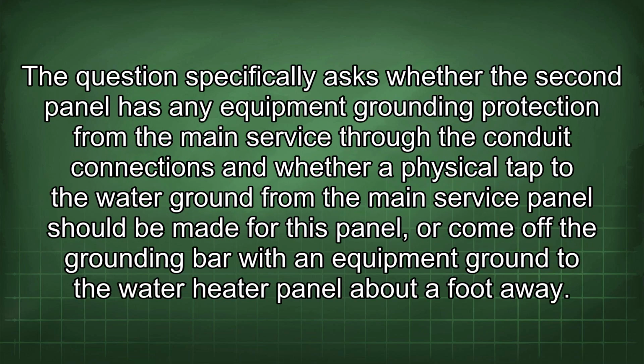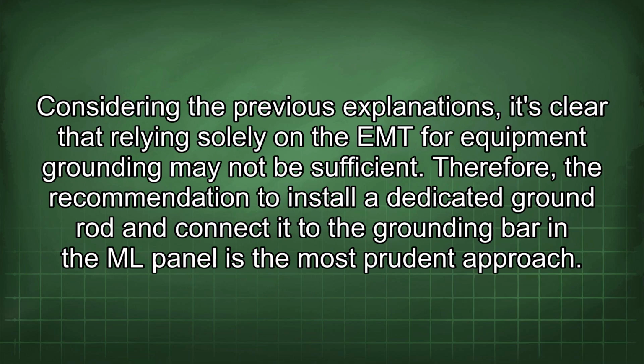The question specifically asks whether the second panel has any equipment grounding protection from the main service through the conduit connections, and whether a physical tap to the water ground from the main service panel should be made for this panel, or come off the grounding bar with an equipment ground to the water heater panel about a foot away. Considering the previous explanations, it's clear that relying solely on the EMT for equipment grounding may not be sufficient. Therefore, the recommendation to install a dedicated ground rod and connect it to the grounding bar in the ML panel is the most prudent approach.